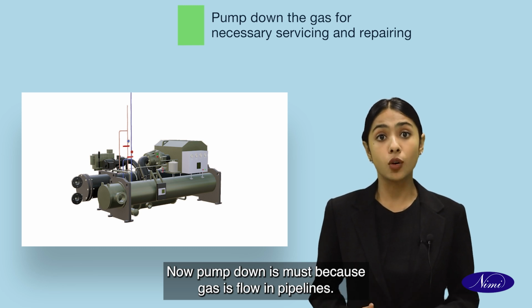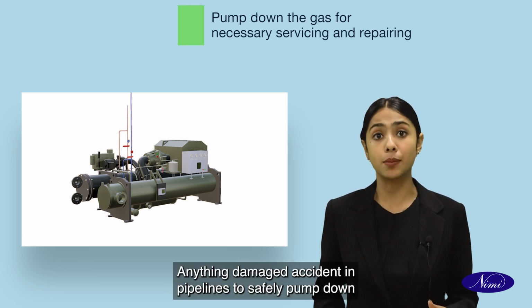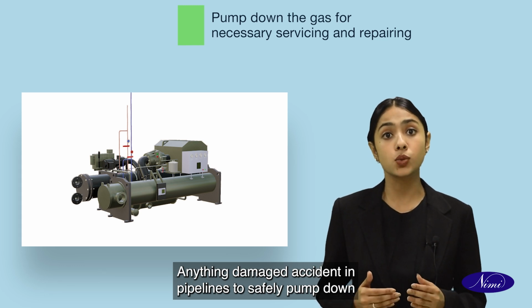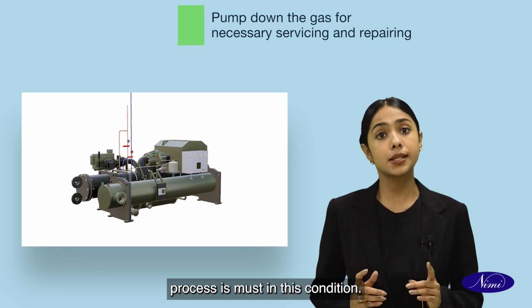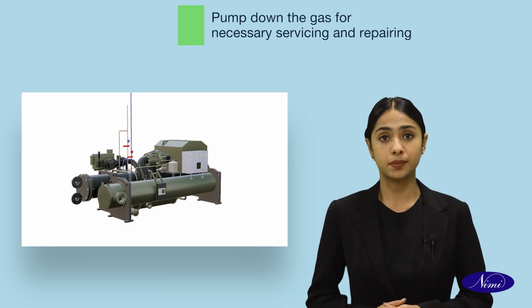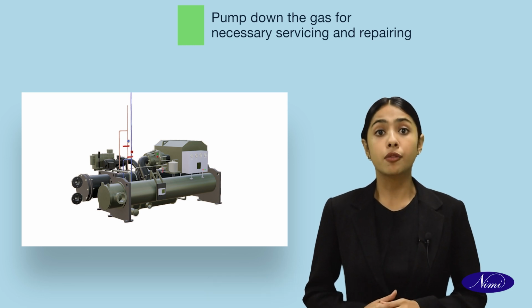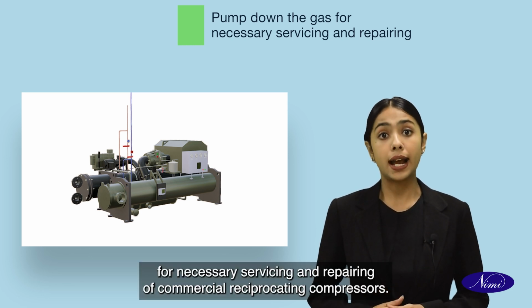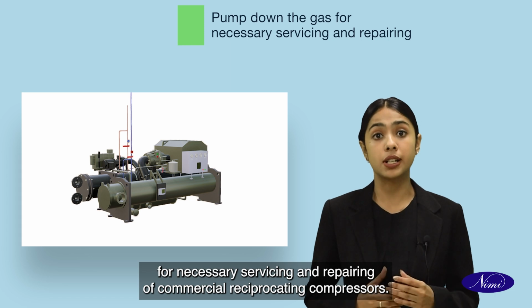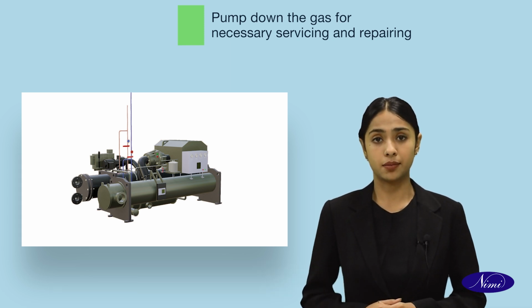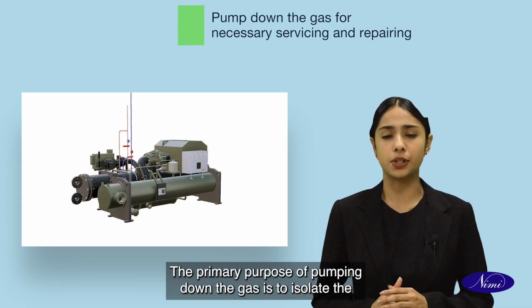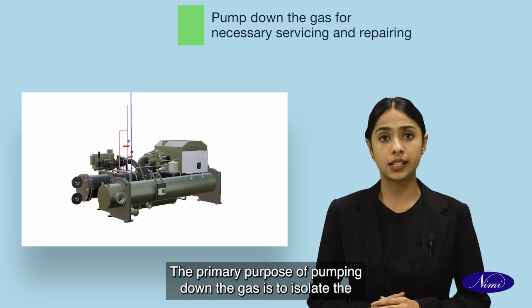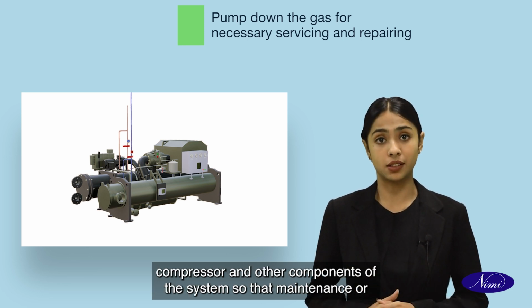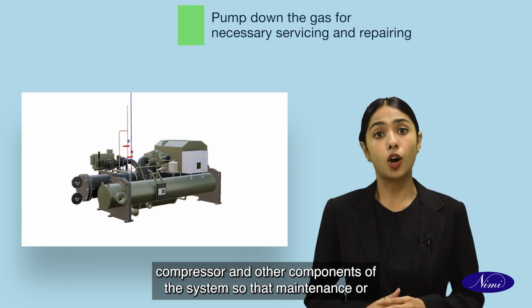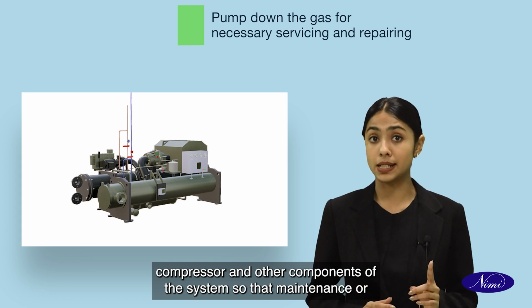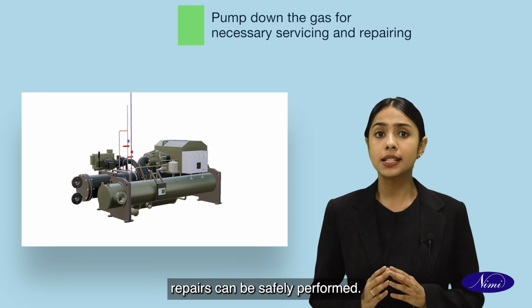Because gas flows in pipelines, in case of any damage or accident in the pipelines, a safe pump down process is a must in this condition. This is often done for necessary servicing and repairing of commercial reciprocating compressors. The primary purpose of pumping down the gas is to isolate the compressor and other components of the system so that maintenance or repairs can be safely performed.